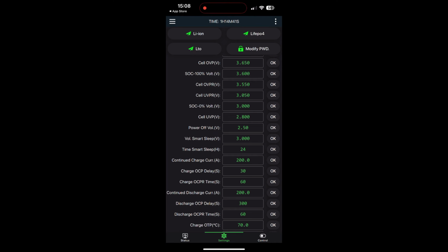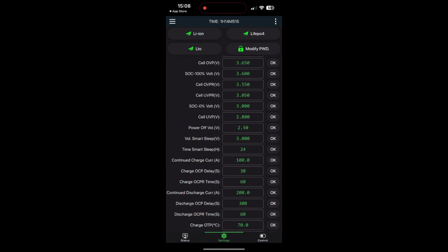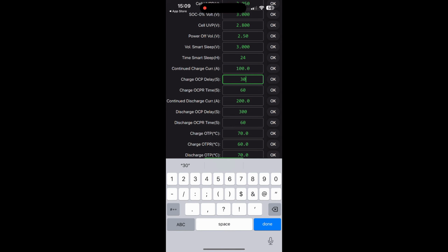I'll give an example. I should probably set that to 100 because I've got 200 amp hour cells and 0.5 C is 100 amp. Now look, you can charge them higher, but this is the optimum charging rate. So you can set that to whatever you want. Okay, over current protect delay. So the top setting there, which is 100, it will sustain 100 amps for at least 30 seconds before the BMS will disconnect.